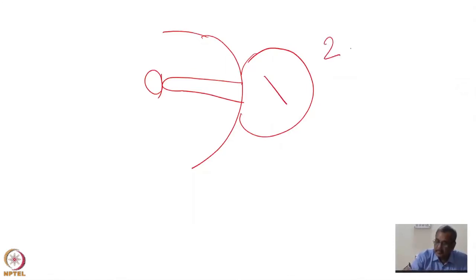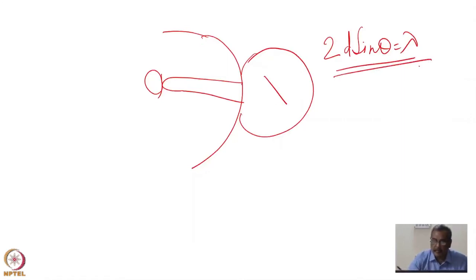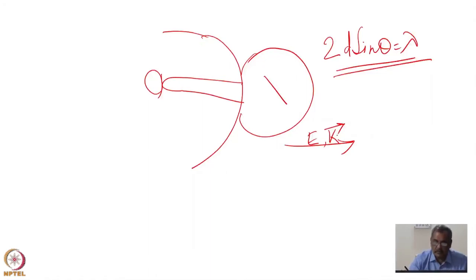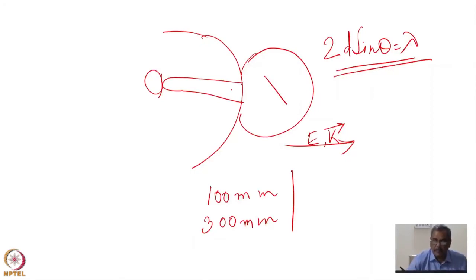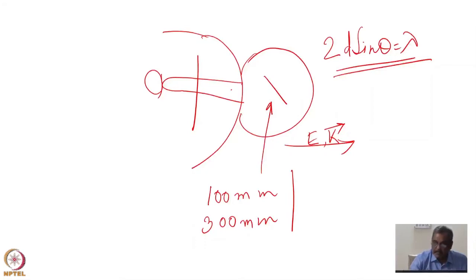The monochromator reflects the neutron beam and chooses a monochromatic wavelength, because in scattering we need a direction- and energy-defined beam. Before the beam reaches the monochromator, inside the beam path — these beamlines are around 100 mm or 300 mm diameter — we should have the facility to close down the beam, because sometimes you might need to approach this path and it is directly open to the reactor core where very heavy radiation can come. All these come inside the beam path: the inner gate and what is known as in-pile collimators.